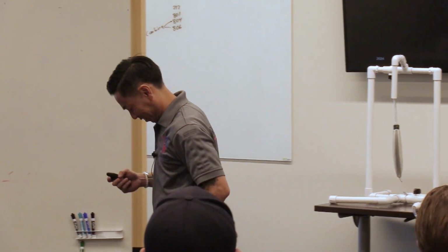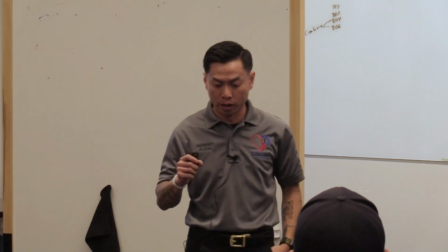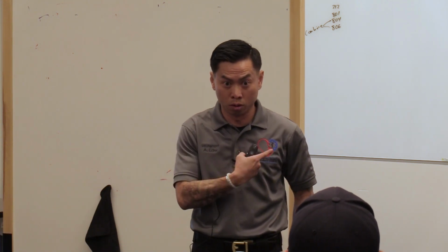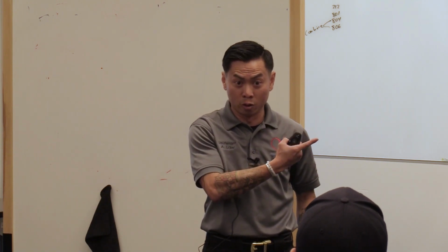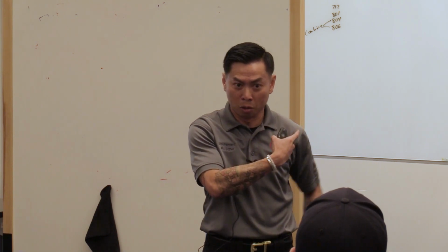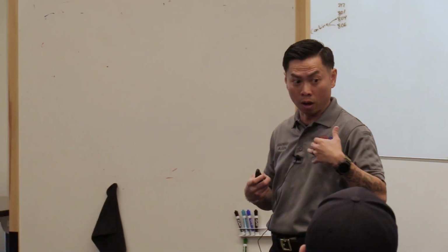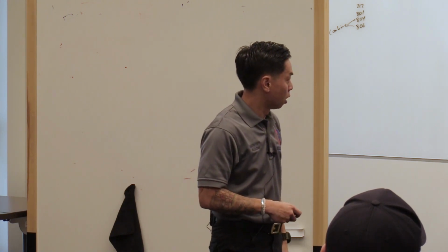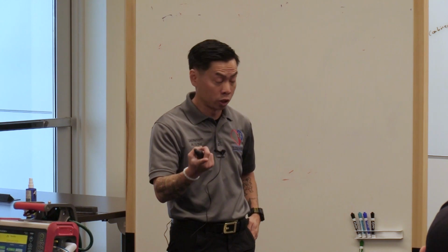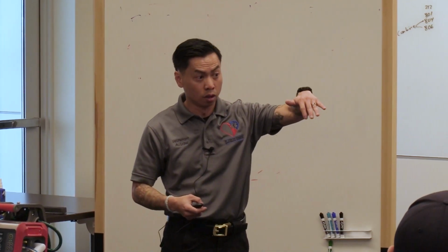How about, let's say mine fails, I come up to a service center, pick up a new one, get a call, and it hasn't been checked in a month. Is there anything that says this has to be checked? Yes. Well, there's no definitive rule, but again, it's safe practice, right? So if you took a piece of new equipment, the first thing I would do is to do that. Because the whole reason that you dumped the monitor or the ventilator you just did was because it failed that test, right? So it wouldn't make sense to take a new one and go. So if you received a different one, I would try to perform those tests just to make sure it's not user error, circuit, or, you know what I'm saying? So yeah, if it is the first exposure to the current ventilator you have, it would be in your best interest to do those 2 tests, or at the change of every new circuit. So like this circuit was there, we go and use it on a patient, we come back, we put everything together, we put a new circuit on, then you do those 2 tests.